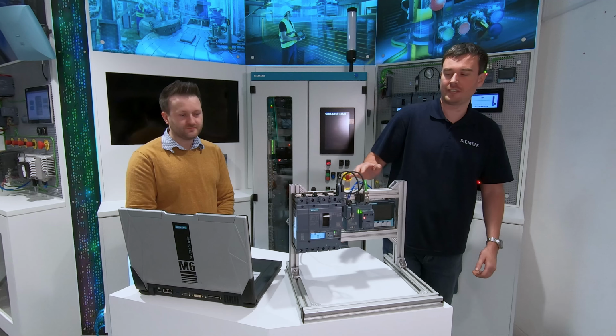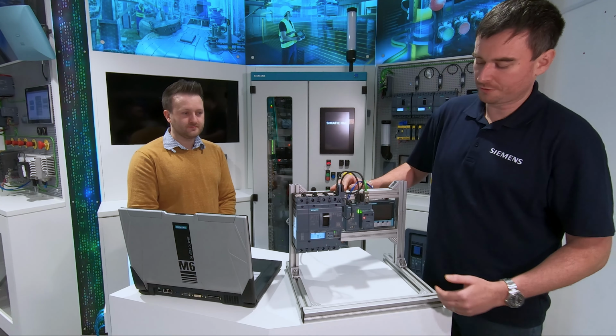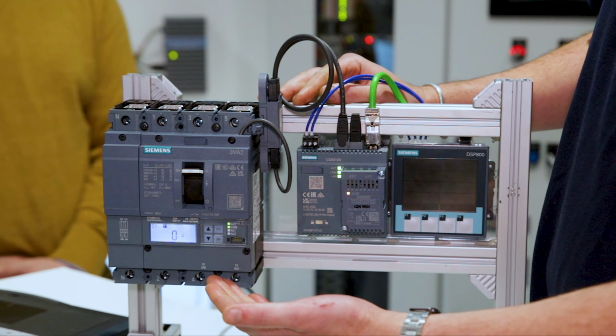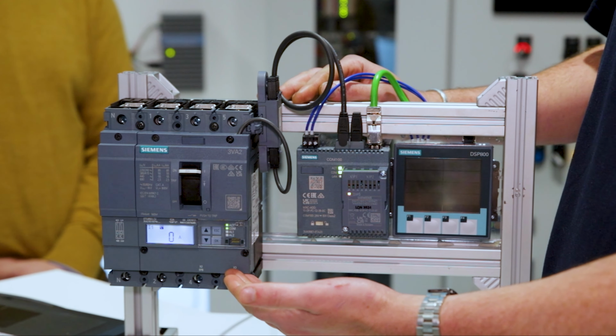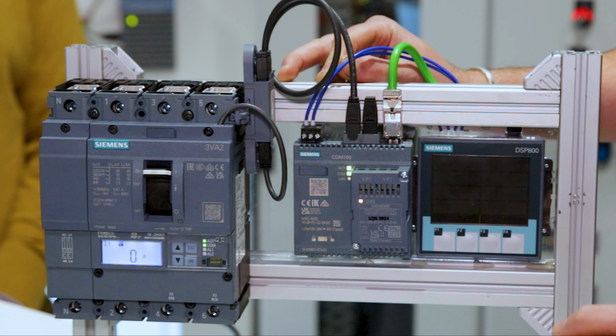Okay, so this is our 3VA2 demo rig. On the front here, we've got a 3VA2 with an ETU 850. Now you'll see this is powered up currently. That's because it's externally powered from the COM100 with 24 volts. It can also be powered through active pass-through current if you are in a live application. It can also be powered from a test device, which is the TD300 or 500.